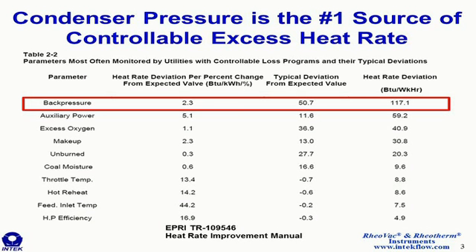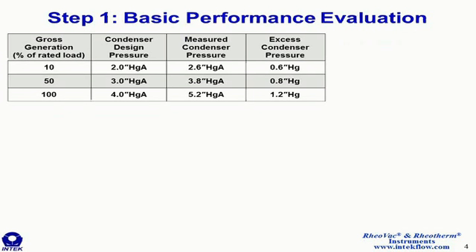So in order to find out how much of an impact can be made, an analysis of the condenser performance is the first step of the process. Well, with instruments that are commonly found on condensers, such as bulk inlet temperature, bulk outlet temperature, a measure of the condenser pressure, and some way to either measure or calculate the cooling water flow rate or turbine exhaust duty, you can calculate the total performance degradation.